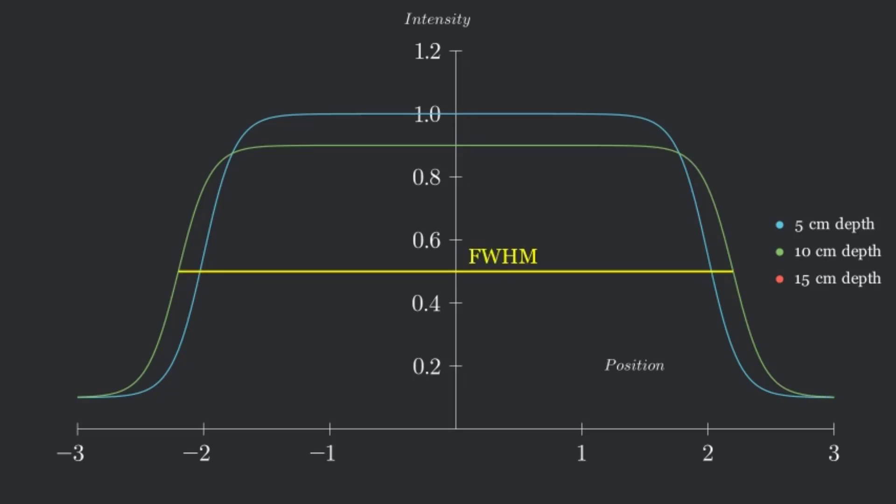And if we measure that same beam profile at different depths, we will have a different field size. So typically, when we define a field size, we're talking at a particular depth, isocenter.